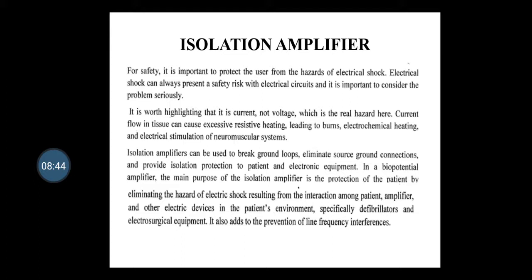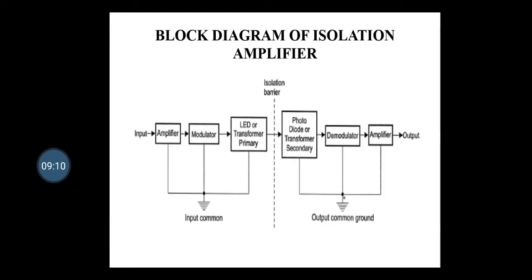Isolation amplifier can be used to break ground loops, eliminate source ground connections and provide isolation protection to the patient and electronic equipment. In a biopotential amplifier, the main purpose of the isolation amplifier is the protection of the patient by eliminating the hazard of electrical shock resulting from the interaction among patient, amplifier and the electric devices in the patient environment, especially defibrillators and electrosurgical equipment. It also helps in the prevention of line frequency interference.